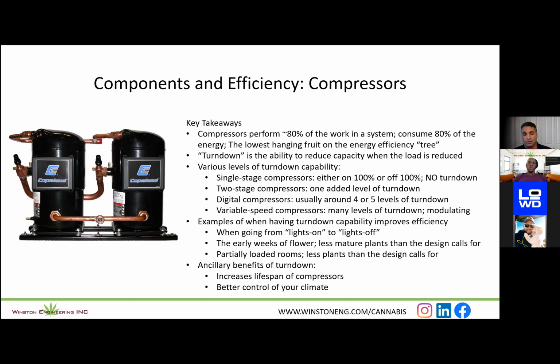Another situation is you're going to design these units for the most mature, worst case scenario, right? That's going to be your most mature plant with the most amount of irrigation and the highest level of lights. In the early weeks of flower, that's not when you're going to see that. So it's nice to have some turn down capability there. And then again, on partially loaded rooms, for whatever the reason. If you're only at 50% in the space or 75% in the space, that unit's still designed for 100%. So the ability to turn down is a very easy way to improve your efficiency on any project, really.